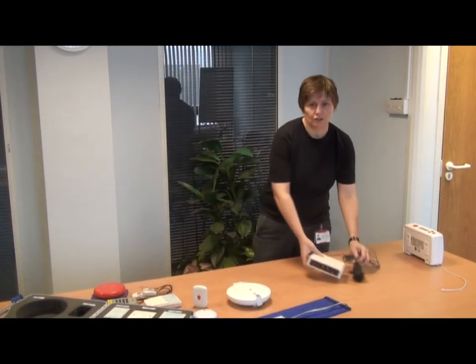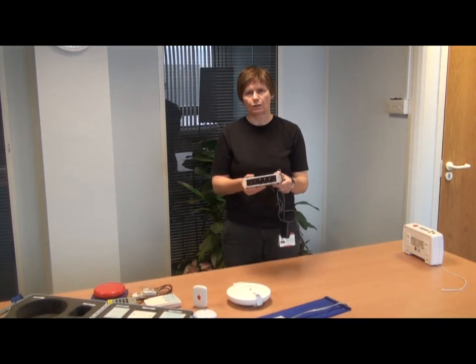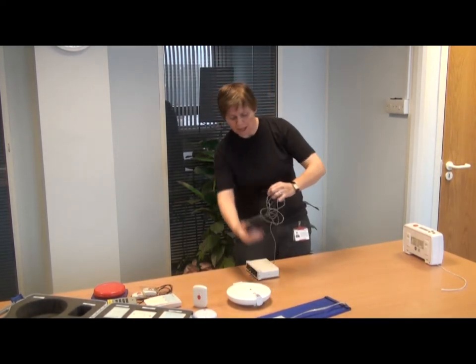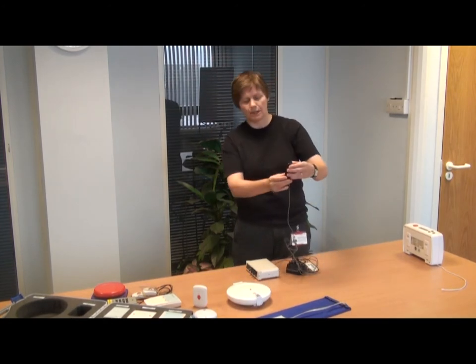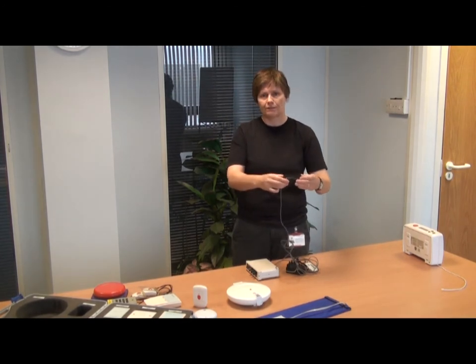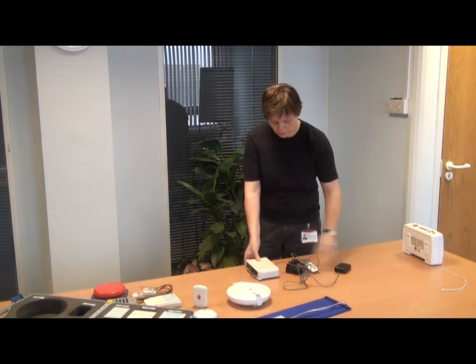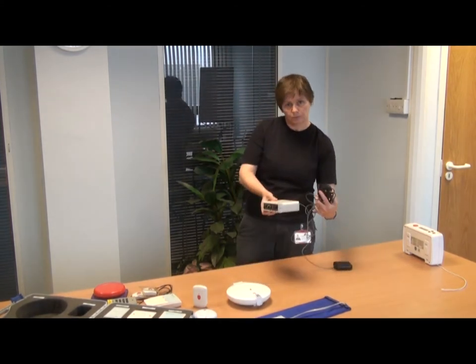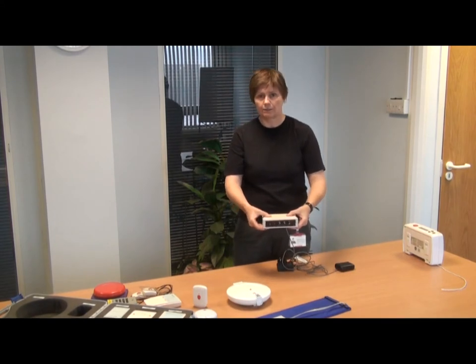This device is called an epilepsy monitor. It only detects tonic-clonic seizures. This paddle goes between the person's inner bed, between the base of the bed and the mattress, and this is the paddle that detects the vibration associated with the tonic-clonic seizure. The device plugs into a normal electric socket, and this is the box that sits at the side of the person's bed.